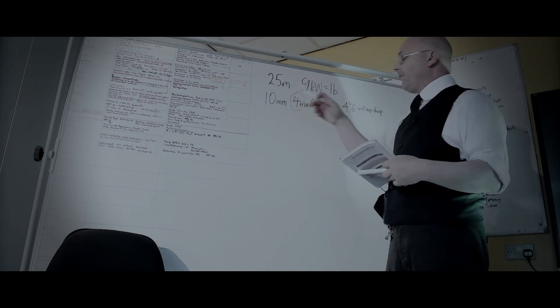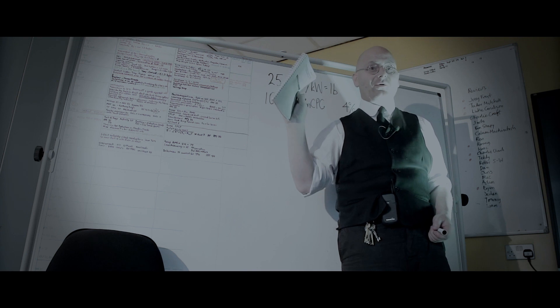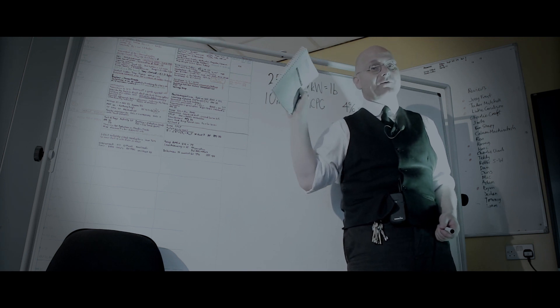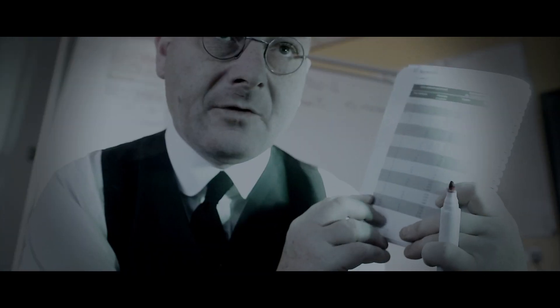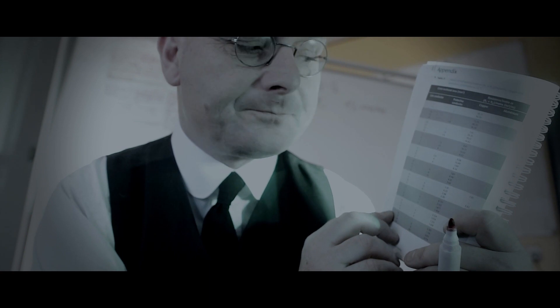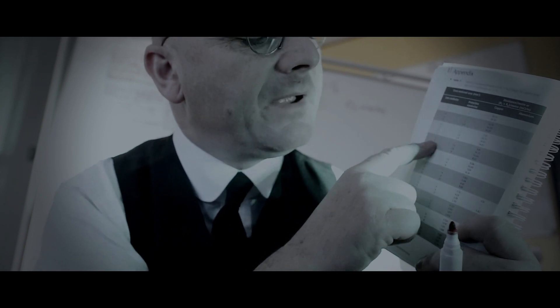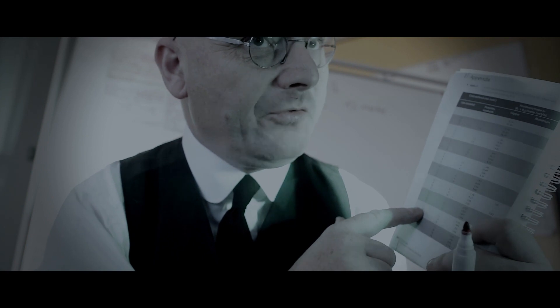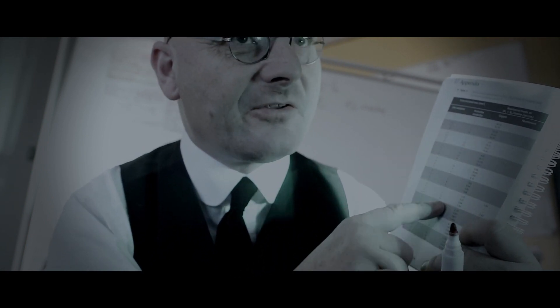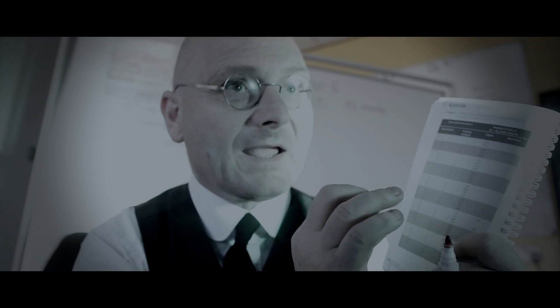We've got 25 meters of the 10 millimeter CPC. The first thing we're going to do is look at Table I1 in this book. Table I1 looks like this. Down the first column we have a list of sizes of conductors, from 1 millimeter through to 35 millimeter. But we also have the column for the protective conductor size. If we use that column, we don't have to do a calculation of out and back — it's already been done.